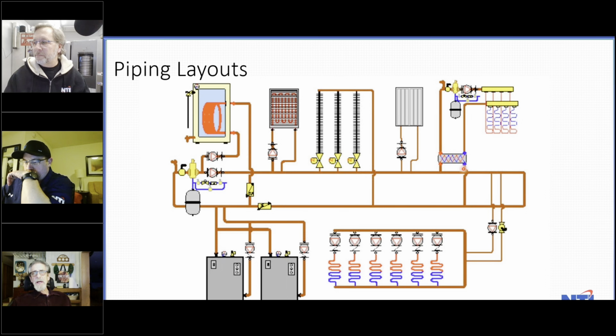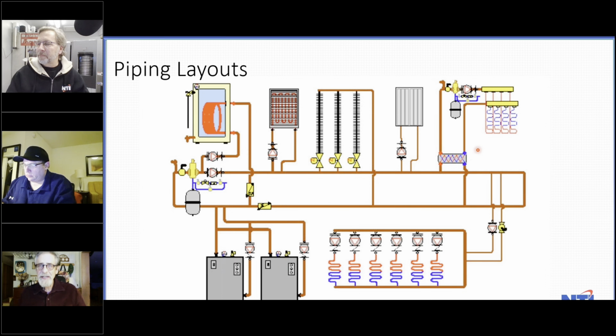exchanger. And again, because we've isolated the Snowmelt system with a heat exchanger, we also then have to have an expansion tank and a spiral vent and its own pump and everything out there as well. So understand, the moment you isolate with the heat exchanger, you're basically creating a second system. As far as the Snowmelt system is concerned, the heat exchanger is the boiler in this particular case. And then finally, there's some low temperature injection mixing of 6 radiant zones.